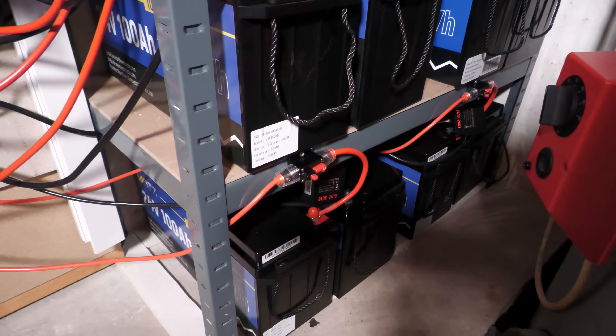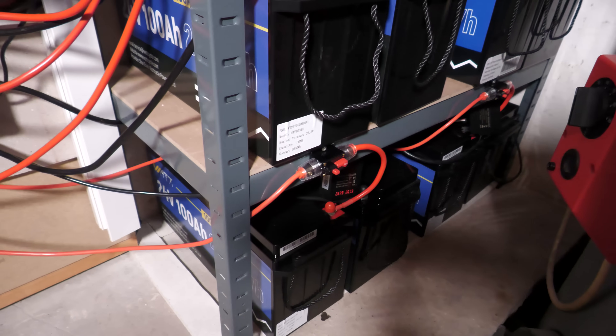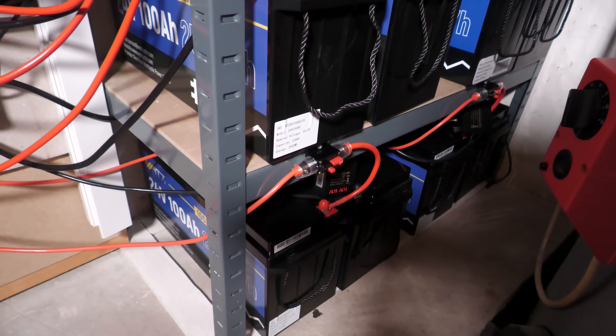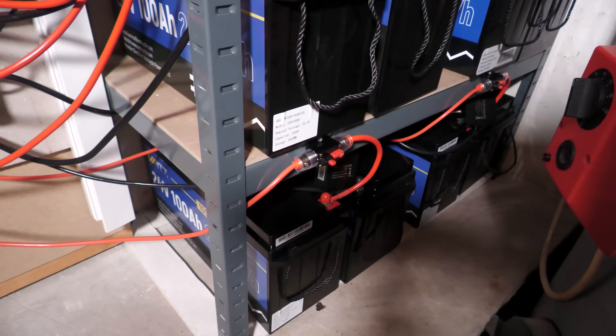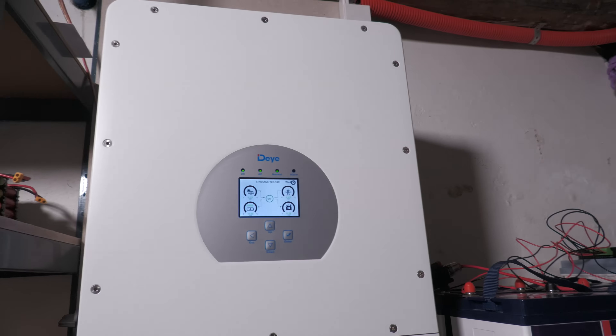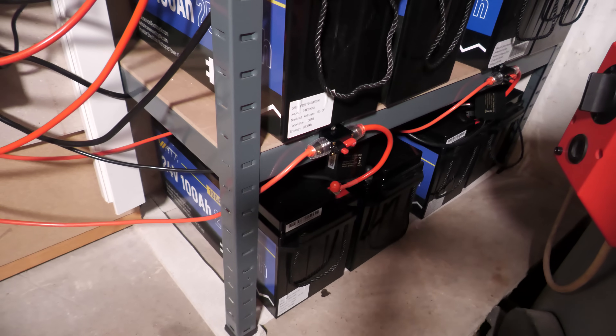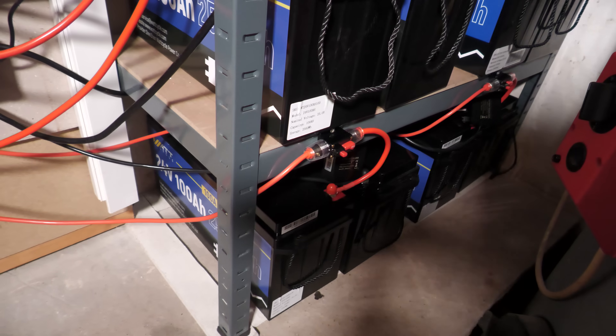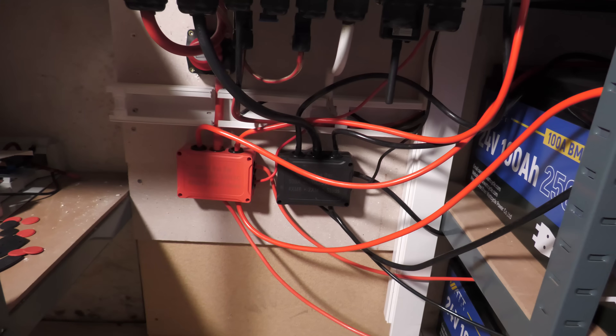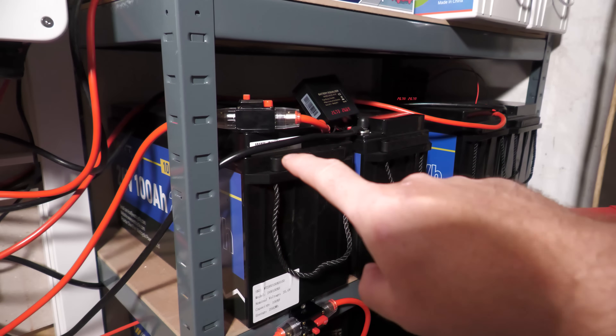I like to mess around and try to sell power when it's expensive, so when there's money in it I tell the inverter to sell power and it makes a few bucks - I'm very amused by that. But when I do that at 6000 watts, I've noticed it has a tendency to flip the breaker - it flips the ones that are closest to the bus bars.